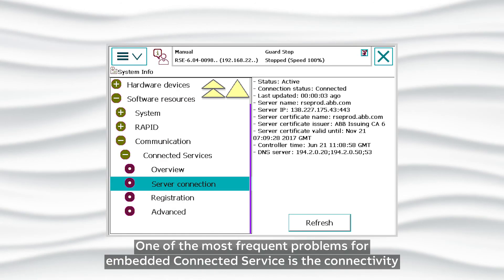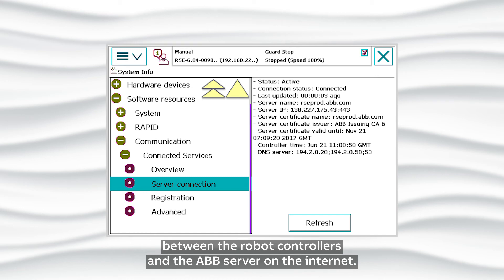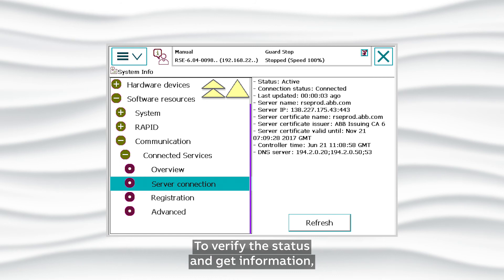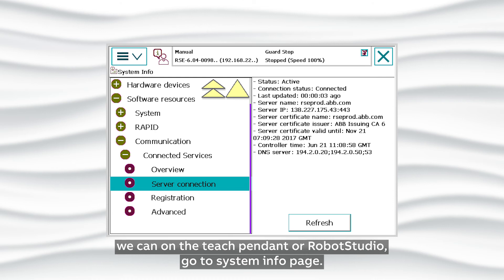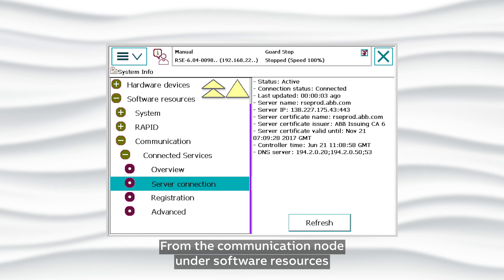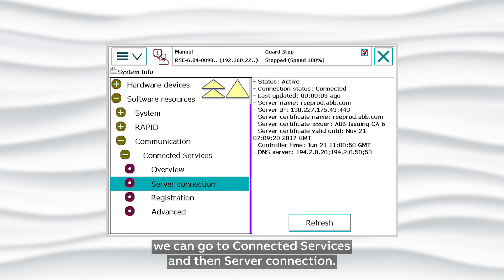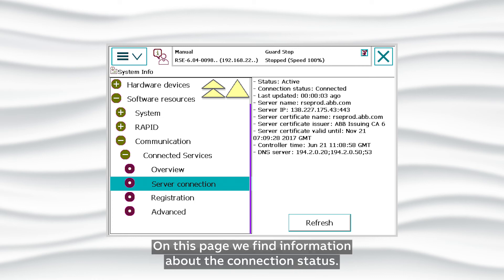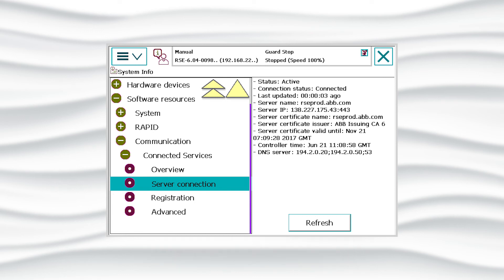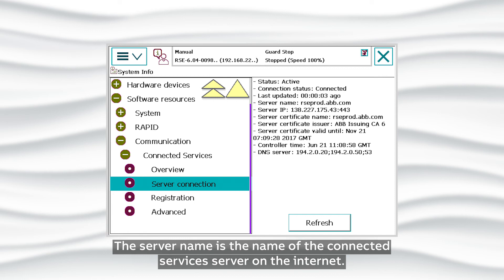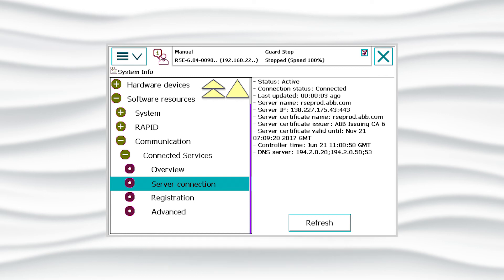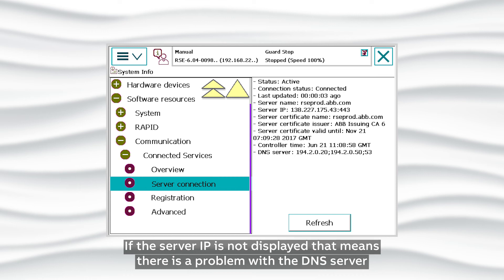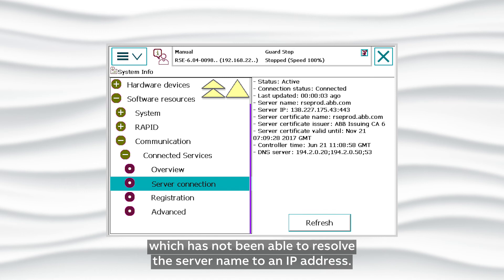Troubleshooting. One of the most frequent problems for Embedded Connected Service is the connectivity between the robot controllers and the ABB server on the internet. To verify the status, go to the System Info page on the teach pendant or RobotStudio. From the Communication node under Software Resources, go to Connected Services and then Server Connection. On this page, we find information about the connection status — whether it is connected, not connected, or trying to connect. The server name is the name of the Connected Services server on the internet; the server IP is its IP address. If the server IP is not displayed, that means there is a problem with the DNS server, which has not been able to resolve the server name to an IP address.